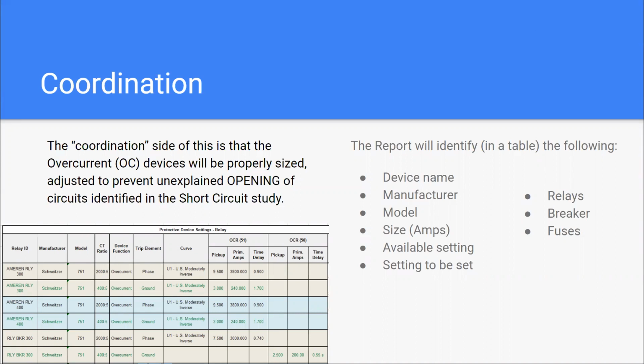That's an interesting call out on the emergency side. In OSHPD, they require it on the emergency side, but you also have to make sure the normal side on the transfer switches is fully coordinated, because it serves the emergency branches, which further complicates it even more.